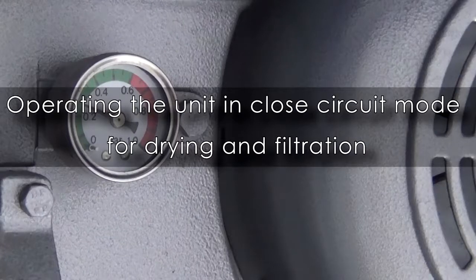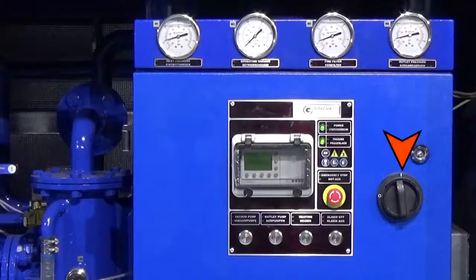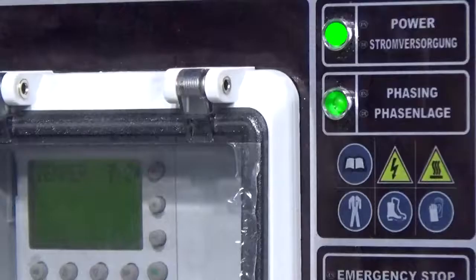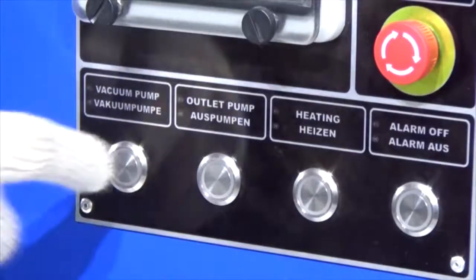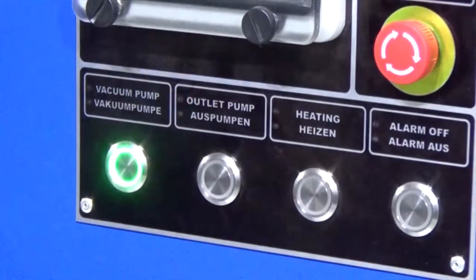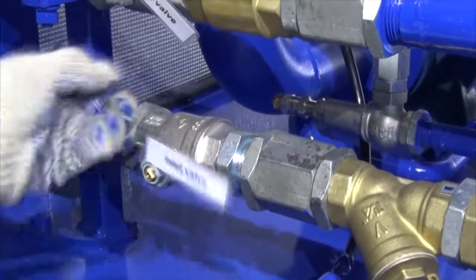Operating the unit in closed circuit mode for drying and filtration. 1. Set the thermostat to the 70 degrees Celsius mark. 2. Power the unit by turning the power handle to the on position. Power and phasing lights must be on. 3. Start the vacuum pump by pressing the vacuum pump button. 4. Open valves MV1, MV4, and MV5.